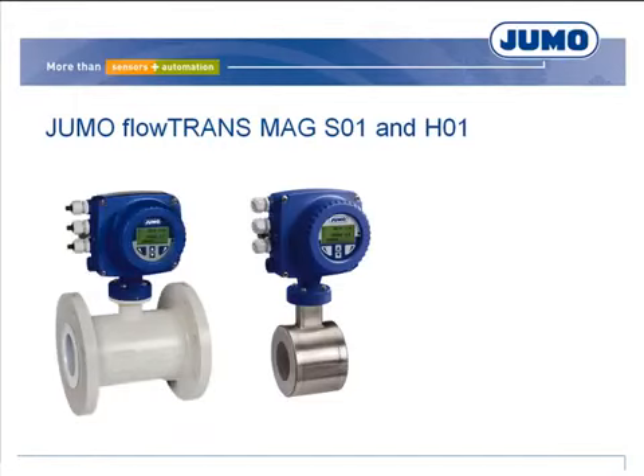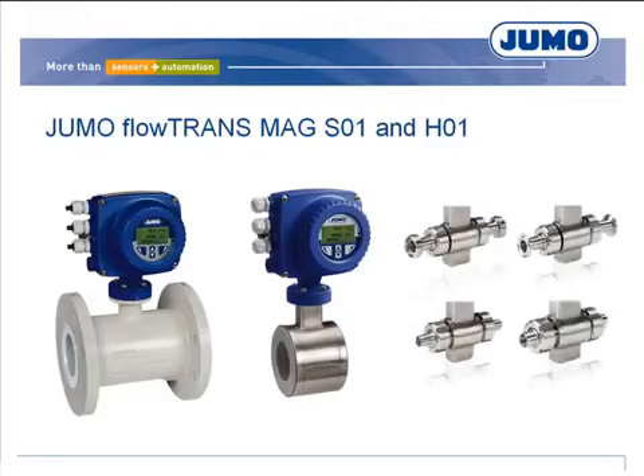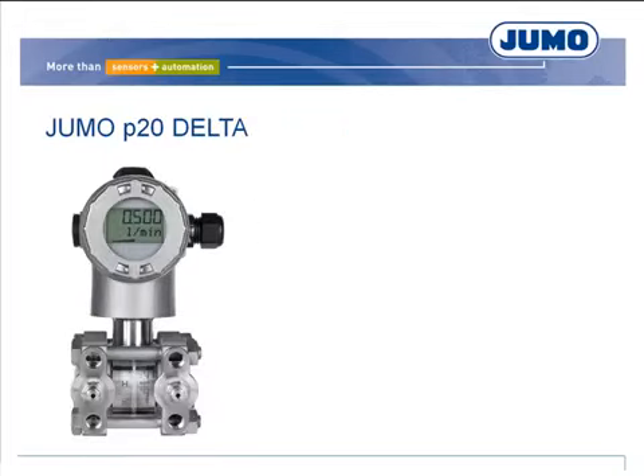It is available as a standard model S01 with flange connection, as well as a hygienic variant H01 with corresponding process connections. The device is composed of the transmitter and the measuring tube with an integrated sensor and must be ordered for the respective pipe diameter. The sensor is available in various linings and therefore suitable for a variety of applications, even for viscous or highly abrasive media with a minimum conductivity of 5 microsiemens.